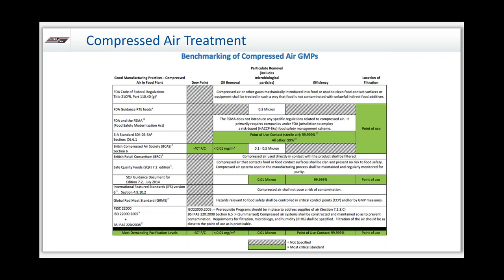If you're looking at the FDA and the FSMA, they don't really have strict regulations, but they want you to base it on a risk-based approach. What some people feel is clean might differ from others. So we compile everybody's opinion and take the most demanding purification levels. At the bottom of this slide you'll see negative 40 for dew point, 0.01 milligrams per meters cubed for oil, 0.01 micron for particulates, and we'd like to see 99.999% filtration retention, specifically at the point of use.